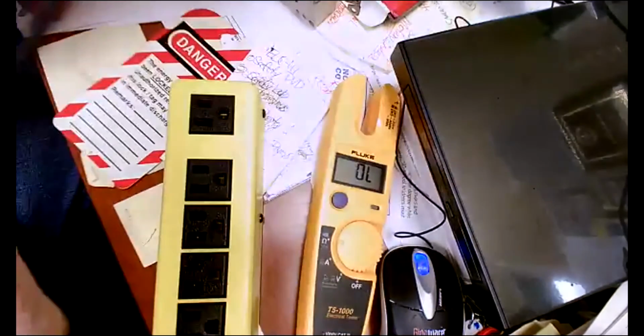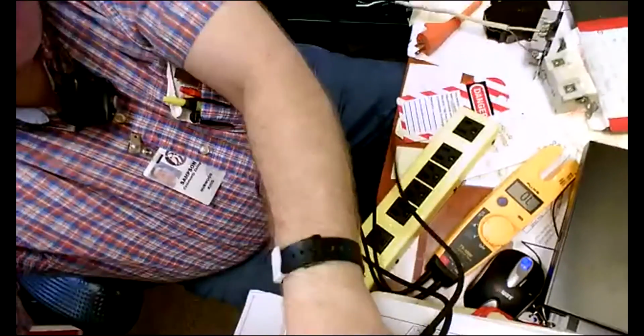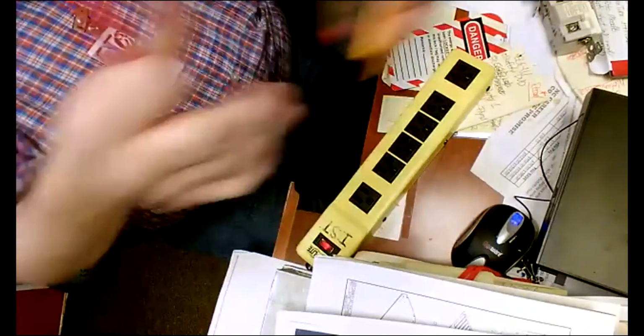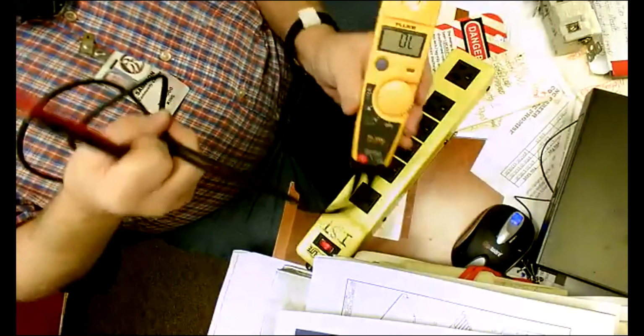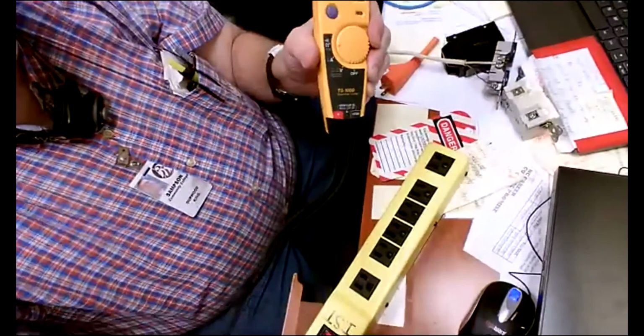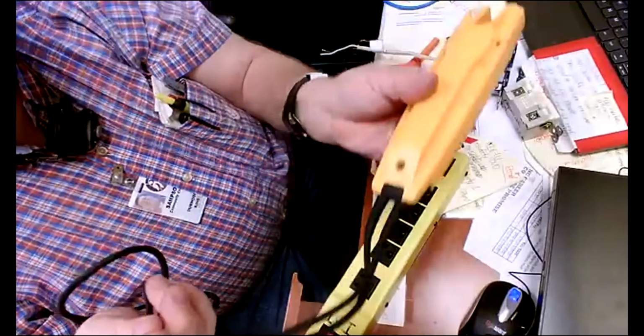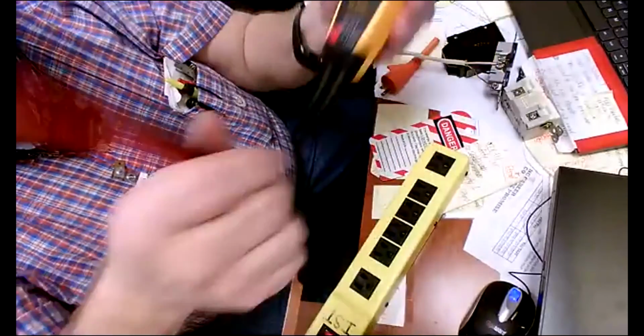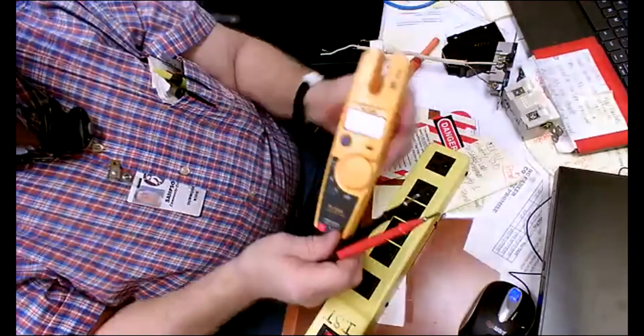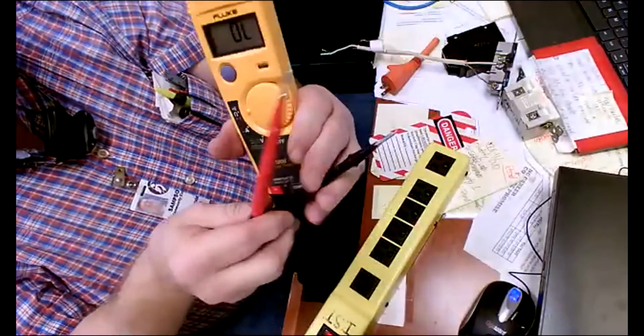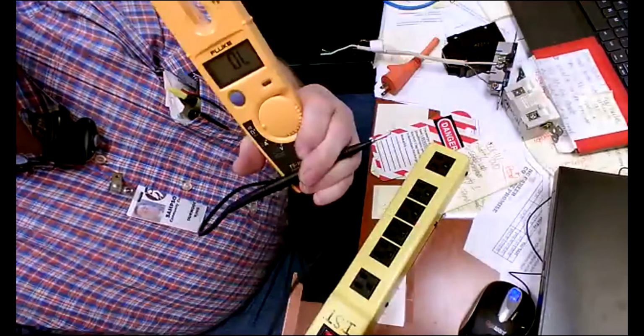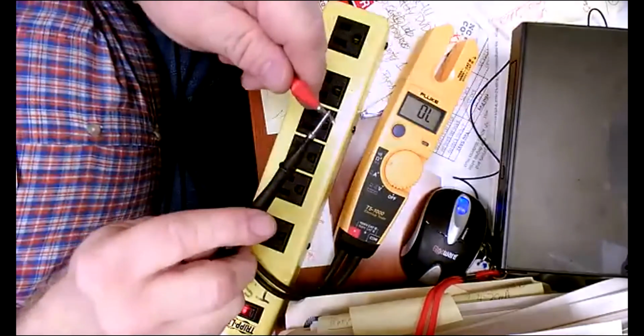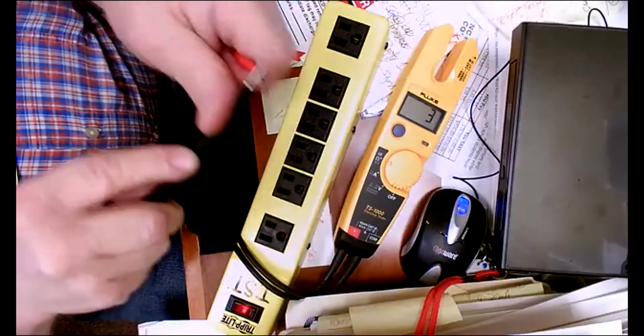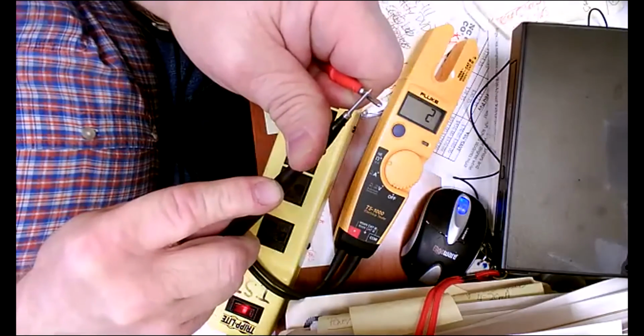Now, the way you can actually check the resistance of your test wires, of your test leads, let's move the camera up. Because sometimes that can get you, if it's not right. Now look, this meter has test leads that are built into it, and the test leads themselves have resistance. So if you want to see what the resistance is of the leads, then you just put these two together. And let's go back down here. Set that down. You just touch these together. And see, that says 3.2.